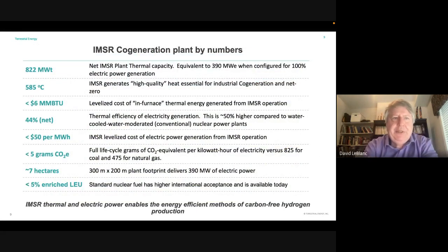Some cogeneration numbers here: if all you want is thermal energy, that twin unit can provide about 822 megawatts thermal. That's less than double the number I said earlier, because that's when we use some of our own heat to make our house load electricity. We're supplying that at about 585 degrees, as either salt or steam just slightly below that. In-furnace heat cost relates to under $6 per MMBTU. Please remember, though, that doesn't mean $5 MMBTU gas would beat us, because that gas price is not in-furnace—when you burn natural gas, 20% of the energy goes up the smokestack. So when you look at the boiler costs and those losses, we can directly compete with roughly $4 per MMBTU gas. The net efficiency is just over 44%, which is much, much higher than water-cooled reactors.